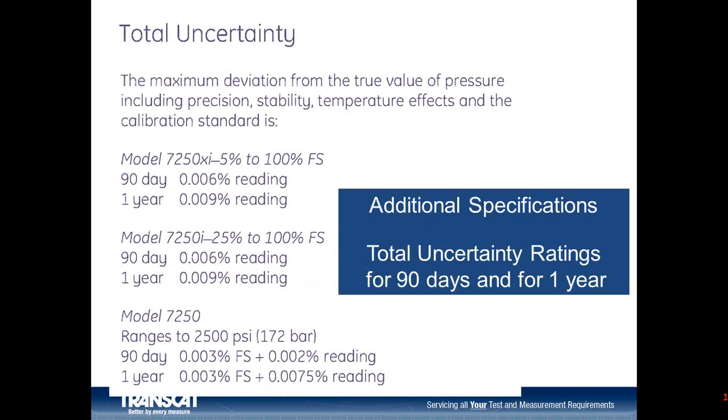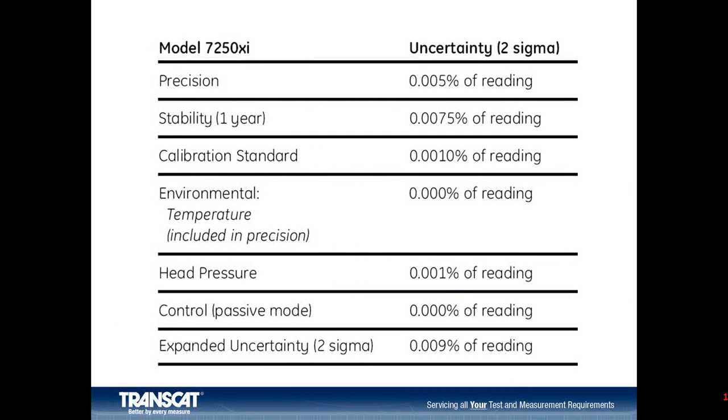Referring back to the specifications, the technical information from the manufacturer of this device, there's additional information that tries to account for the uncertainty in the traceability, and as well includes allowances for degradation of the performance over time, a drift allowance. And again, from the specifications, we can see more detail about how this comes about.